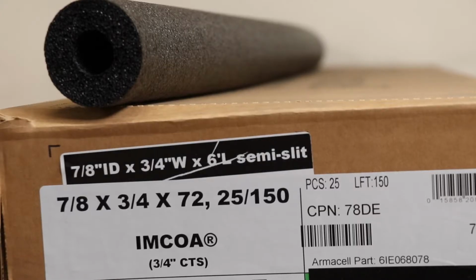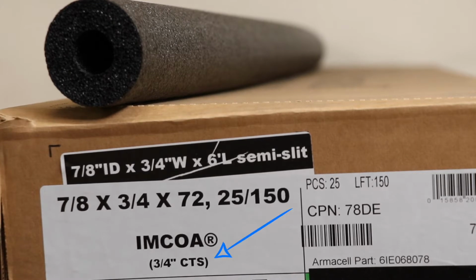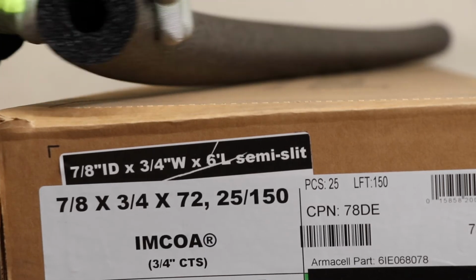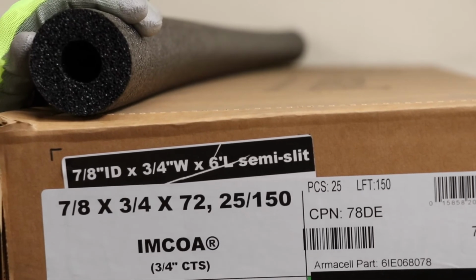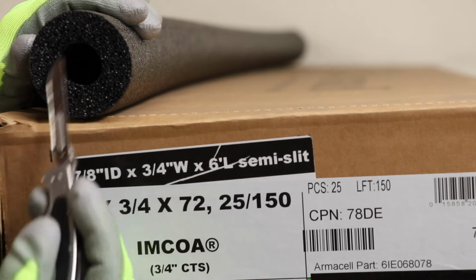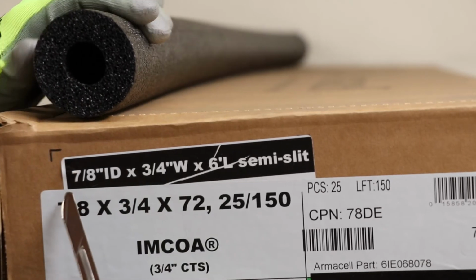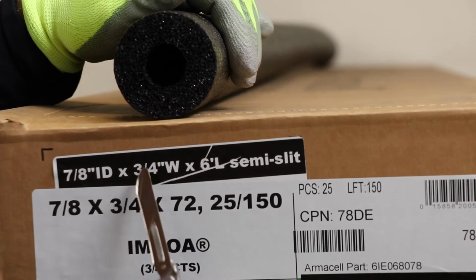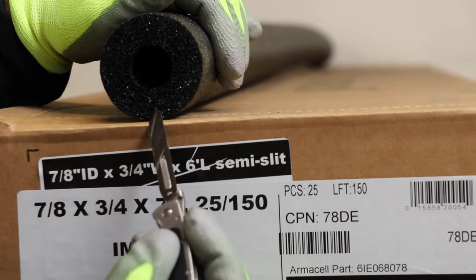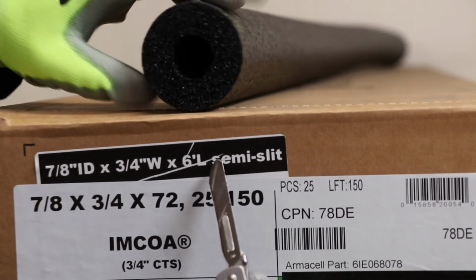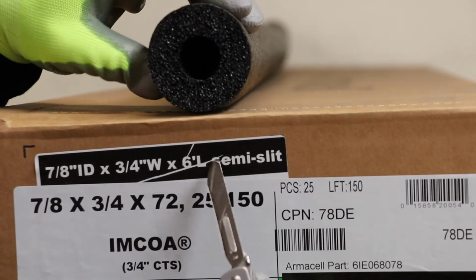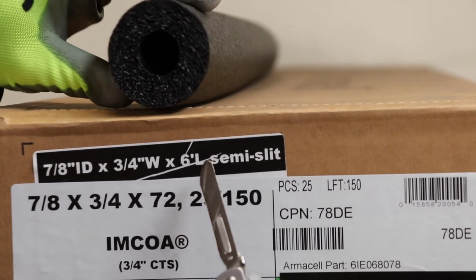All right, here's how most all insulation is read. You can see here where it says 3/4 inch CTS, or copper tube size. We know that the OD of 3/4 copper tube is 7/8, so the inside of this insulation is 7/8. The next measurement is the wall thickness. You can see this is 3/4 inch wall by 6 foot long semi-slit. Everybody's got a different name for that. It's just half cut. It's all it's saying.